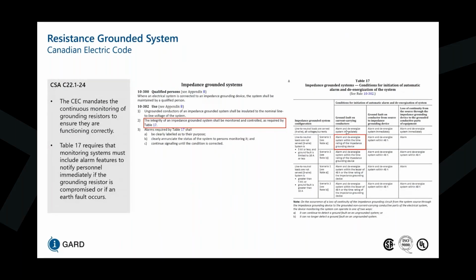Now, the area where a lot of consultants and end users are taking advantage is the second row, where it indicates line-to-neutral loads are not served, so the system is 3-phase 3-wire. The system is at 5 kV or less, and ground fault is limited to 10 amps or less. In this case, for the ground fault scenario, it says alarm and de-energize the system within the time rating of the impedance grounding device. But when we typically specify high resistance grounded systems, we typically go with a continuous rated resistor so that we only have to alarm the condition of ground fault without having to de-energize.